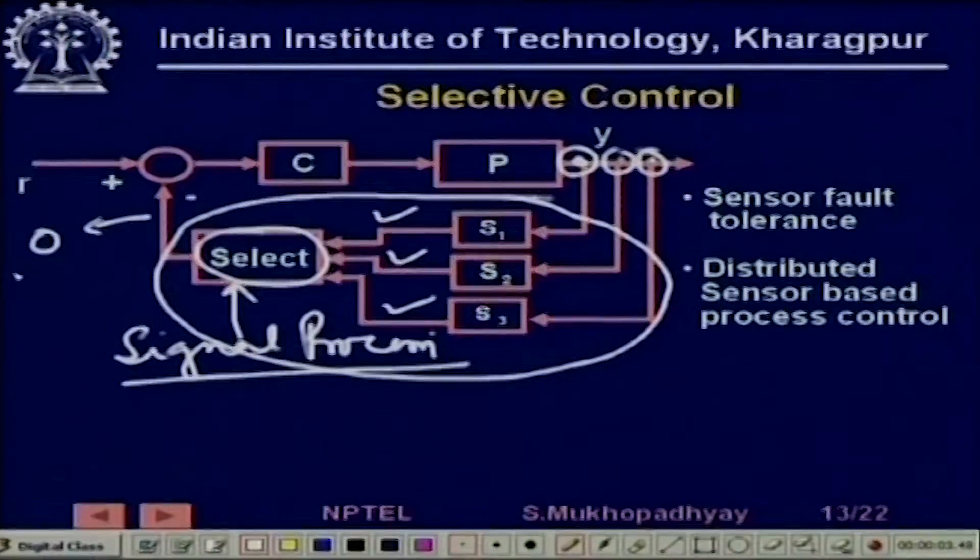In case of room cooling that is the approach — you choose the maximum value. There are even other applications. For example, sometimes very catastrophic effects can occur in feedback control loops if one of the sensors fails. If there was a single-sensor feedback and the sensor failed — some wire torn, something burned out, or an electronic circuit problem — and this signal goes to zero due to failure, the controller will have no way of knowing it. It will simply see an error and try to drive the process unnecessarily, but that driving will not improve the value because the sensor is no longer sensing. In such cases, industrial accidents may result and equipment may get damaged.